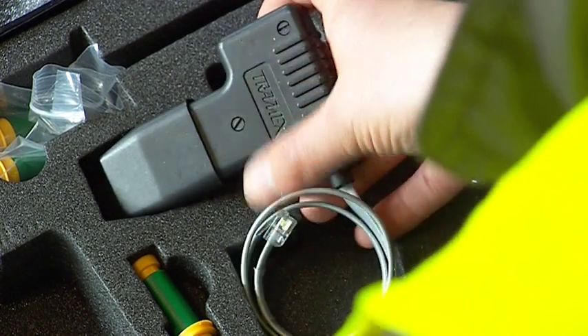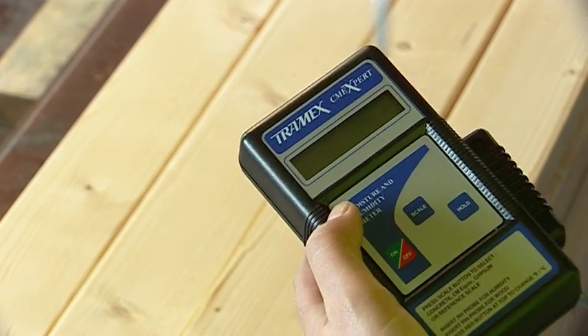The plug-in pin type wood probe, which when plugged in automatically switches the CMEXpert to pin probe mode, is designed to take instant measurements of moisture content by percentage in wood and wood products.